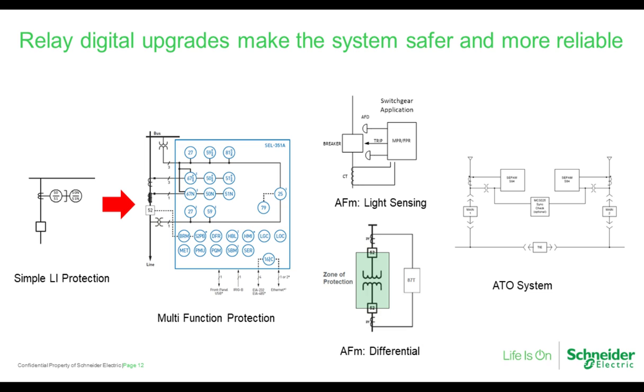Some of the things that we can also add: new state-of-the-art relays can include light sensing for arc flash mitigation. We can either add a separate relay for arc flash light sensing, or some of the relays now have that built into the new solid-state relays. We also can add differential protection, which can protect a system and lower the arc flash incident downstream by having a differential protection relay scheme.